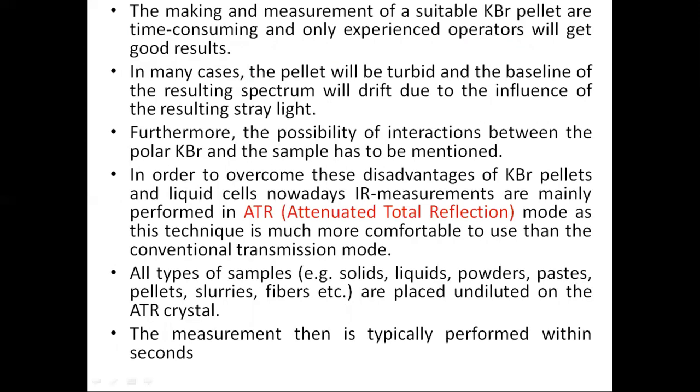The making and measurement of a suitable KBr pellet are time consuming and only experienced operators will get good results. In many cases, the pellet will be turbid and the baseline of the resulting spectrum will drift due to the influence of stray light. Furthermore, the possibility of interactions between the polar KBr and the sample has to be mentioned, because KBr, which is polar in nature, may also react with the sample.